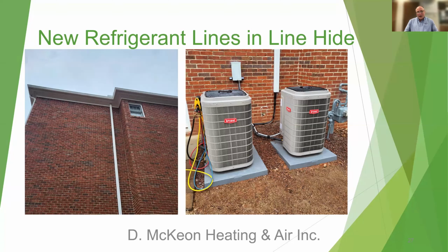If your unit is not level, there is a good view right there. Your unit should be level. If it's not, it needs to be leveled. It can be leveled by just putting anti-vibration pads under the edges of parts of the unit to lift it up and level it. But if you ever do that, make sure that you do not pinch the line set at all. Make sure there's flexibility before you move the unit. Just moving it an inch can sometimes cause a refrigerant leak or something to that effect. So be very careful about that if you're thinking about leveling your unit.